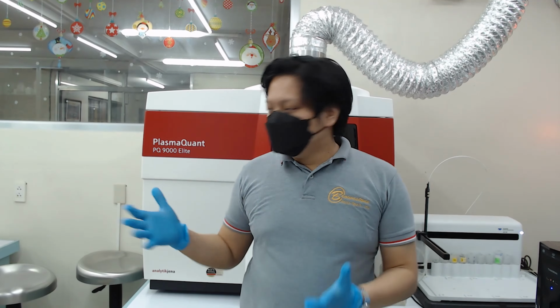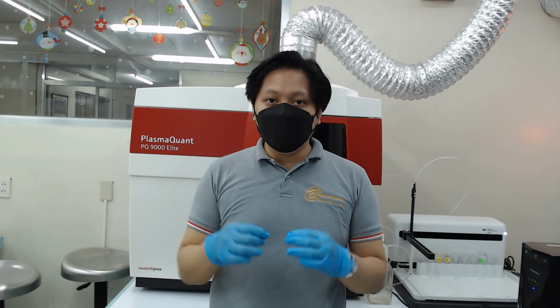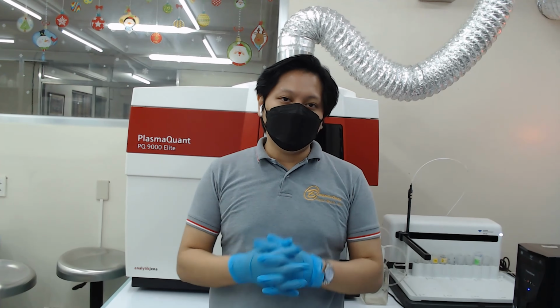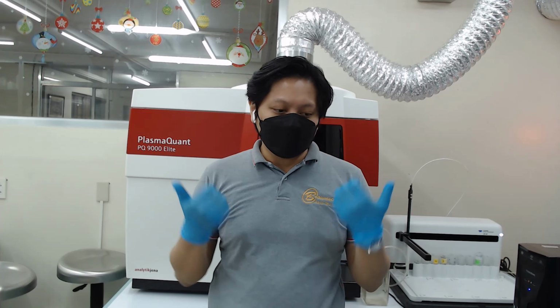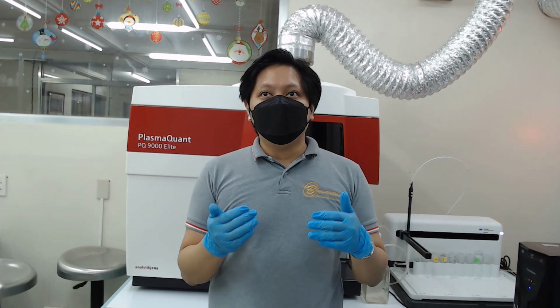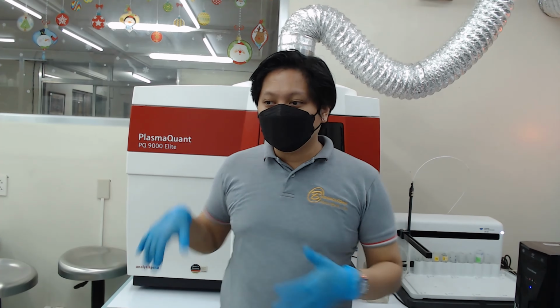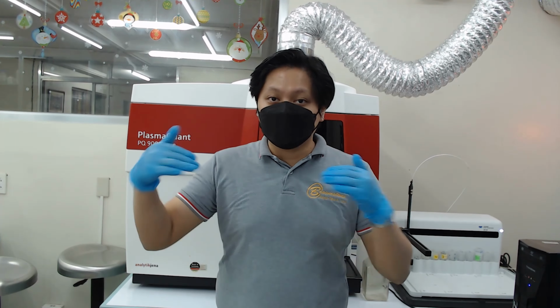So si PQ9000 Elite and as well as the PQ9100 series, meron siyang tinatawag na optical system purge. So when you press the power button, what will happen is that it will start purging the optical system with 2 liters per minute ng argon flow. So this flow is very low, and it's designed for customers na gustong hindi agad mag-analyze. Gusto nila mag-turn on muna ng machine pero hindi pa sila agad mag-analyze, just to start the purging.